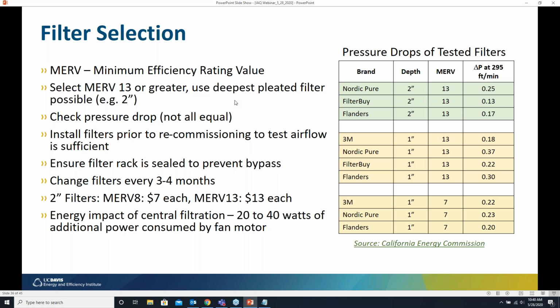I really want to dispel this myth. This is not true in most cases. If you obtain pressure drop data for filters that you're considering buying, you will see that there are low pressure drop MERV 13 filters available, commonly available.